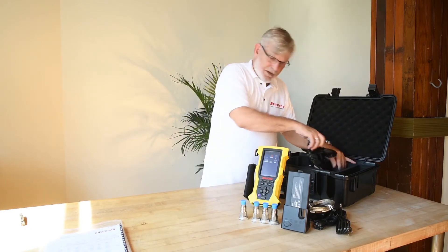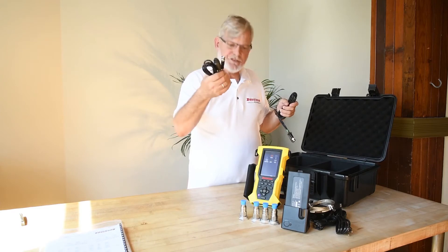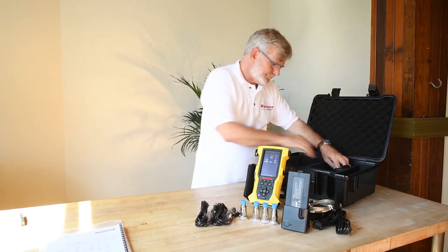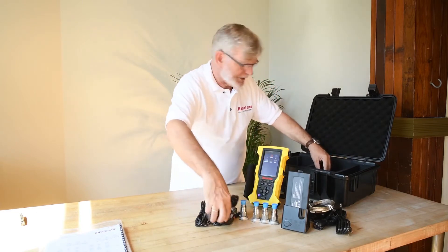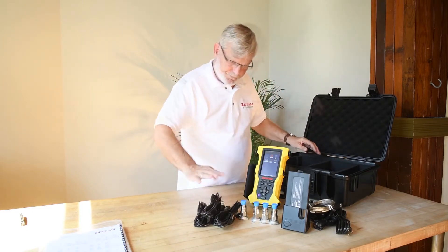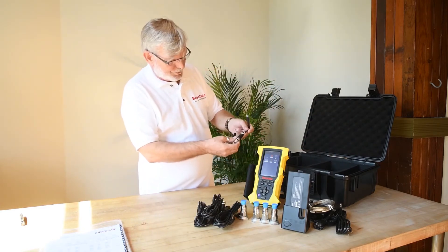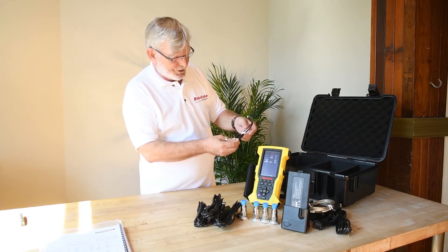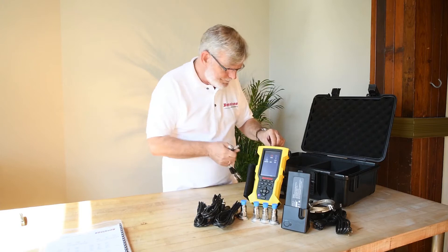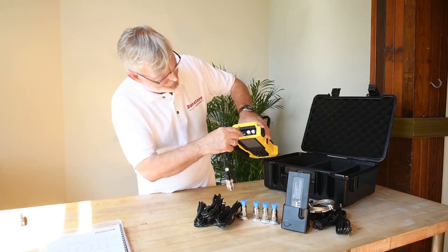Next, we've got the connectors for the sensors — BNC to mil connector. There's one, two, three, and four. There's a breakout cable here with the numbers two, three, and four on them, so that would be for a triax reading. And this Lemo would connect right in here for channels two, three, four.